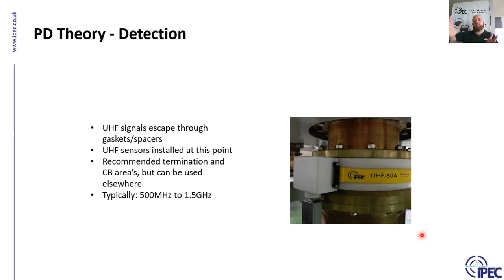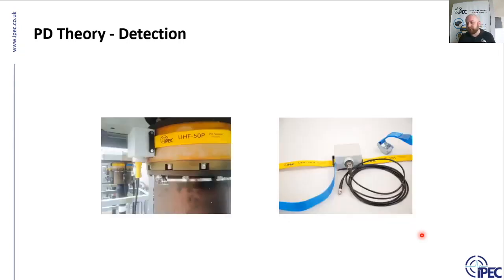Where two compartments of the GIS meet, there'll be a barrier in between, and we install the UHF sensor there. That's where we're going to see this ultra high frequency signal which escapes from within the GIS. There are lots of different barriers around the equipment, so quite often we install them where the customers have the main concern. Sometimes the main concern is in the CT or the VT or the circuit breaker. It depends on the switchgear, and on the history of failures of that type of switchgear. Quite often it's also on the cable termination. Cable terminations are naturally a weak point in any equipment. So I think this picture here is a cable termination, with the sensor installed on the barrier of a cable termination there.